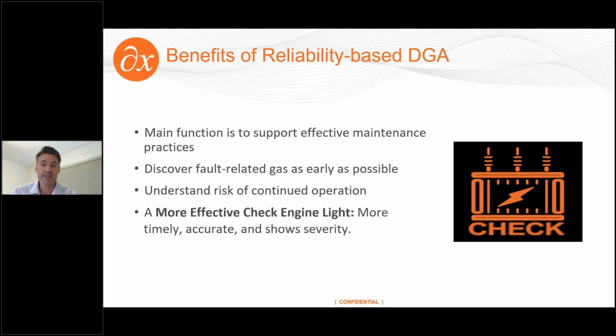So he ran the analysis, and it showed red boxes all over the place in the NEI graph, and the fact the transformer had been overheating for at least 20 years. So Jim told this customer, don't have lunch next to that transformer. So they called him back and said they had no idea the transformer was overheating, and if they would have known this, they would have replaced the fans 20 years ago.